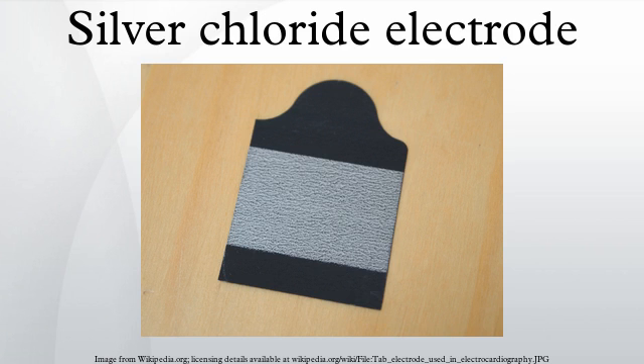The principle of silver-silver chloride sensor operation is the conversion of ion current at the surface of human tissues to electron current, to be delivered through the lead wire to the instrument to read. An important part of the operation is electrolyte gel, which is applied between the electrode and tissues. The gel contains free chloride ions such that charge can be carried through the electrolyte, making the electrolyte conductive for ion current like human tissues. When ion current exists, the silver atoms in the electrode oxidize and discharge cations to the electrolyte, and electrons carry charge through the lead wire.